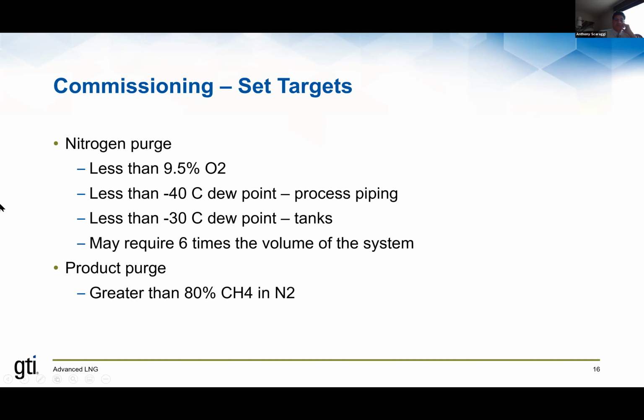And I'm not sure if people understand what that means. The colder the dew point, the less moisture there is in that gas. So by reducing your dew point to a very, very low temperature, what you're actually saying is make sure that the gas in the piping and the tanks is dry before you introduce the cold LNG. Once again, because cold LNG would cause any moisture to freeze out and can block flow and cause damage in equipment. A purge may require using 6 times the volume of the actual system to get a good purge. And once again, that's just an example. There are models that you can use to determine in your system what the actual amount of purge gas would be required to achieve your targets.